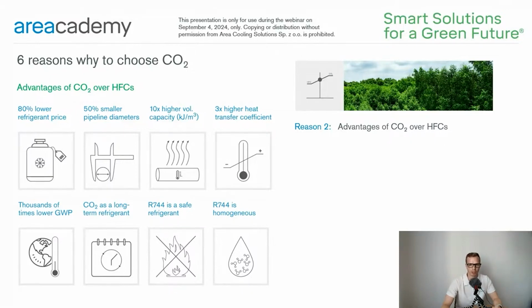The global warming potential factor for CO2 is equal to 1, and it is used as a reference for other refrigerants. This in turn makes R744 refrigerant a long-term solution, since it meets all F-gas restrictions. It is a safe refrigerant because it belongs to A1 group refrigerants, characterized by no flame propagation and low toxicity. And last but not least, the CO2 is a homogeneous substance.